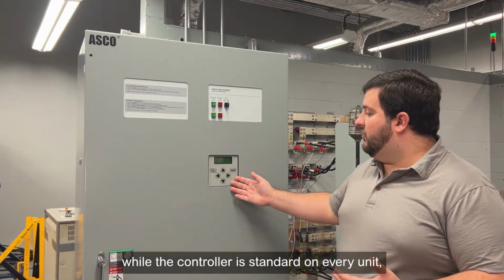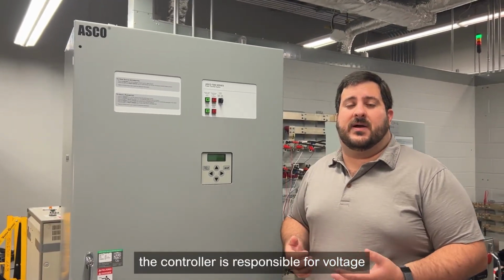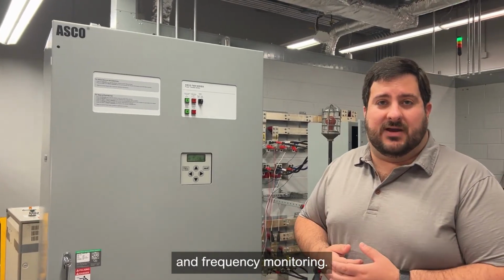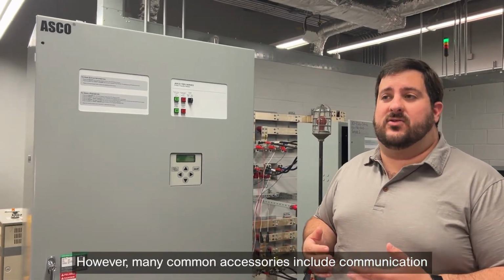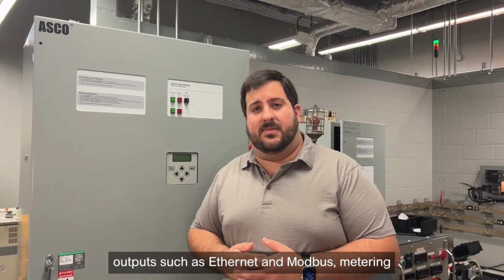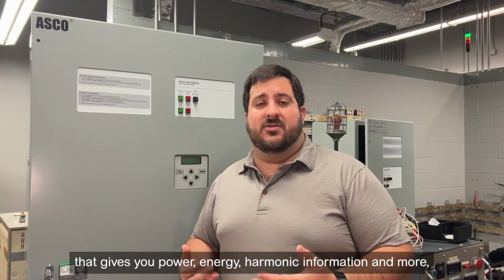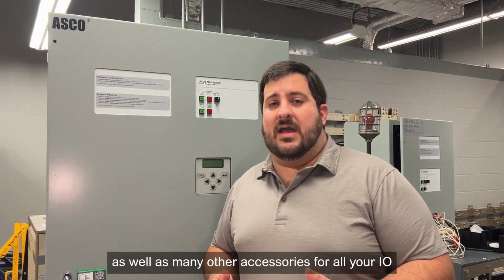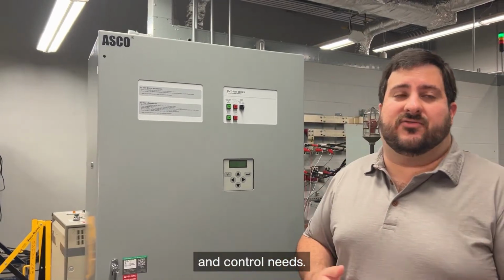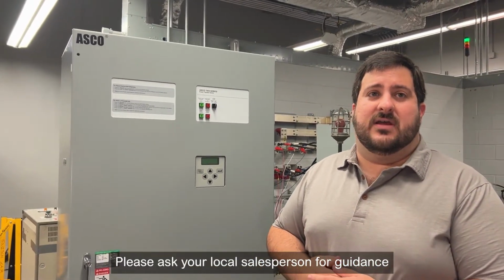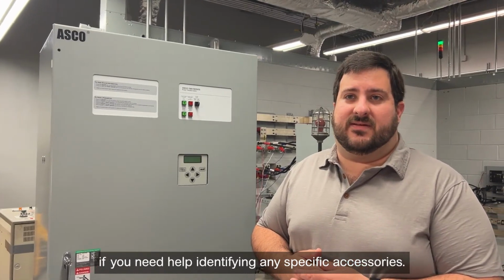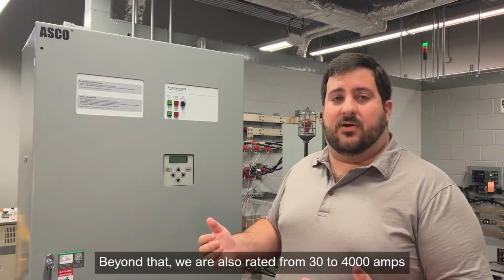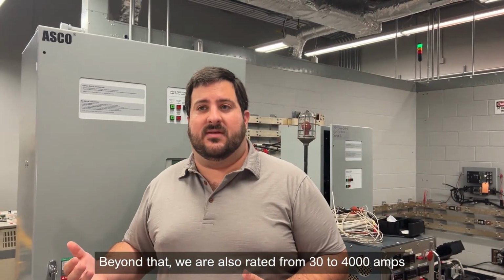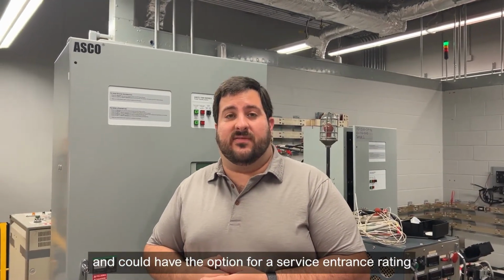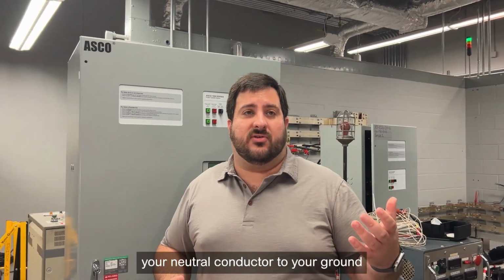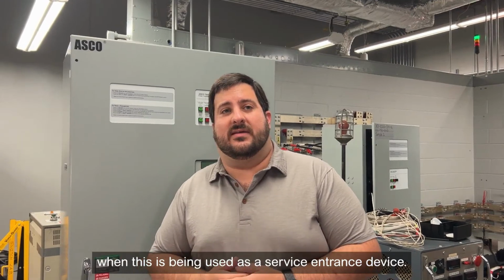While the controller is standard on every unit, the controller is responsible for voltage and frequency monitoring. However, many common accessories include communication outputs such as Ethernet and Modbus, metering that gives you power, energy, harmonic information, and more, as well as many other accessories for all your I/O and control needs. Please ask your local salesperson for guidance if you need help identifying any specific accessories. Beyond that, we are also rated from 30 to 4,000 amps and can have the option for a service entrance rating, which bonds your neutral conductor to your ground when this is being used as a service entrance device.